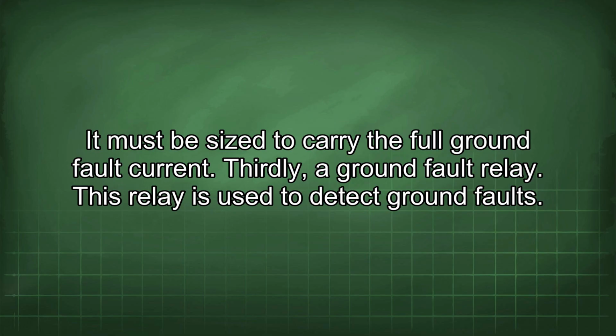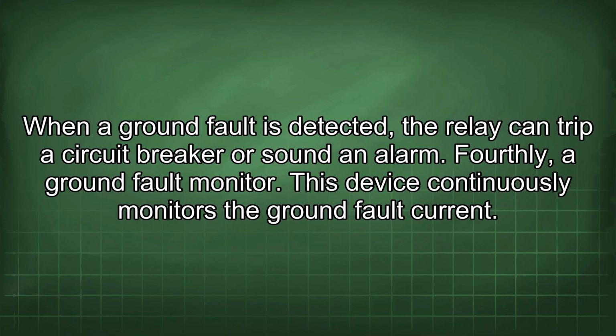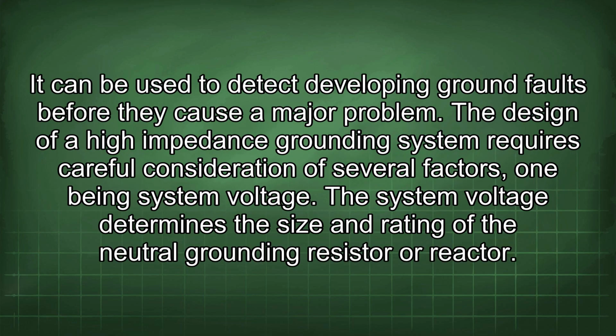Thirdly, a ground fault relay. This relay is used to detect ground faults. When a ground fault is detected, the relay can trip a circuit breaker or sound an alarm. Fourthly, a ground fault monitor. This device continuously monitors the ground fault current. It can be used to detect developing ground faults before they cause a major problem.